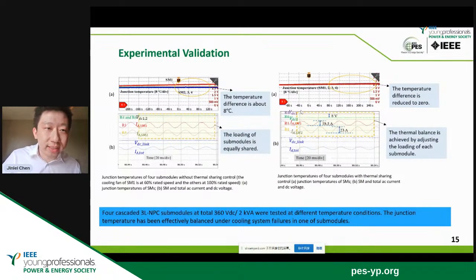So this is a comparison test of the thermal control strategies. In the first one, the junction temperatures of submodules are different due to unequal cooling system conditions. The cooling fan of submodule one is controlled at 60% of rated speed, and the others at the normal 100% rated speed. So we can see that there is a temperature difference of 8 centigrade between these submodules. And after enabling the active thermal sharing control, the temperature difference can be effectively balanced.